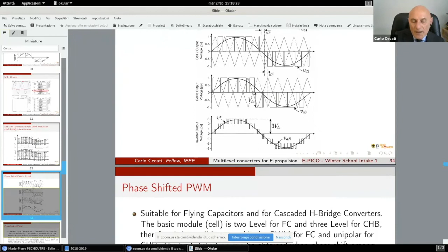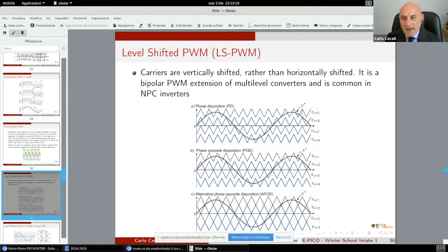There are many techniques which allow improving one or more parameters, so I'll go very fast. For instance, this is level shifted PWM. If you know the concept of PWM, to generate it, first a triangular waveform is generated with a frequency much higher than the expected frequency. In this case, for instance, we have maybe a 50 hertz sinusoid, and the triangular waveform is 500 hertz. But usually the ratio between the fundamental frequency, the expected current frequency, and the modulation frequency is at least 100 to 200 times. So the triangular waveform is very small in comparison, on the time axis, compared with the sinusoid.